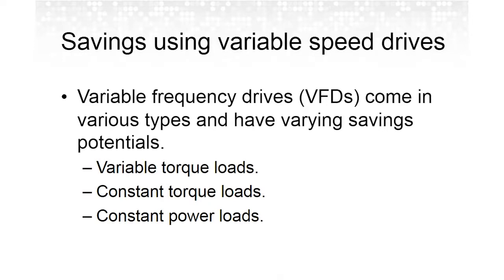Okay, we talked about the codes that are mandating all of this. We can now look a little bit at where the savings actually can occur. For variable frequency drives, it is dependent upon the load. If you have a variable torque load, such as a centrifugal pump or a centrifugal fan, the load torque increases as the square of the speed, and the horsepower increases as the cube of the speed. So therefore, inversely, if you drop the speed, the torque goes down as the square, and the horsepower goes down as the cube of the reduction.